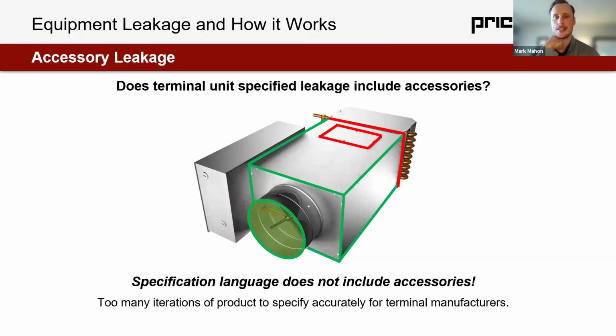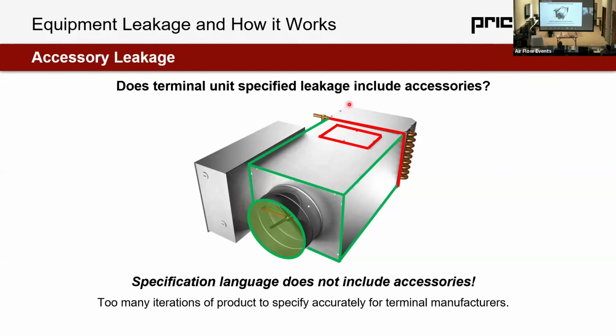So normally those are getting sealed, because I'm going to just give myself a little laser pointer to make sure we're all looking at the same thing here. Can I specify that you guys seal the access door? Like, can I specify leakage rate for that access door upstream and downstream of the coil that you provide me? Absolutely you can, and I'll tell you what I think you should specify in one slide. The transverse joint downstream is getting sealed. So usually the transverse joint upstream is going to get sealed as well.